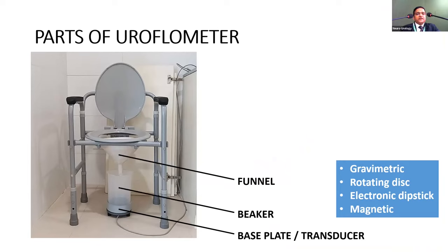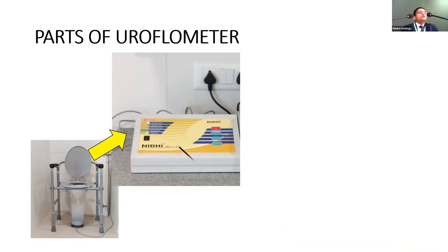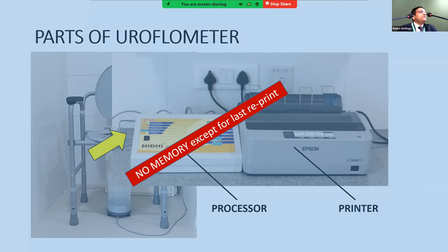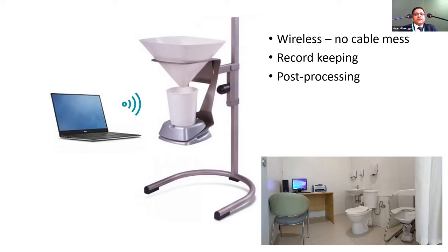The ICS guidelines cover parts of uroflometry: you have a base plate or transducer — gravimetric or rotating disc types are most common, with gravimetric being most prevalent — along with a beaker, funnel, and comfortable seat. Basic uroflowmeters with no sophisticated software are cost-effective but if there's an error, data beyond the last printout is lost. More sophisticated wired or wireless machines are better for record keeping and post-processing, though software errors and Bluetooth connectivity issues can also cause data loss.